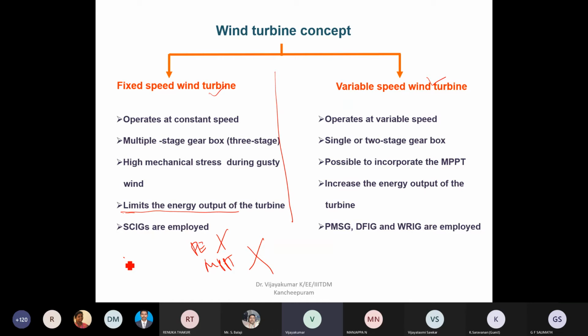Here they will use the induction machine, squirrel cage induction machines, as a generator. For squirrel cage induction machines, the slip range is 2 to 20%. For a small machine, the slip range may be 20%, while for larger machines, the slip range will be 2 to 5%. Only within that 2 to 5% slip range will these machines work as a generator.